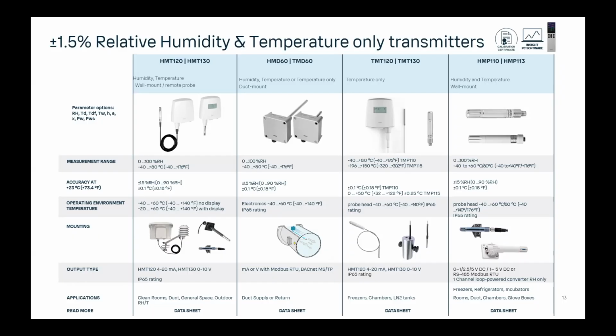It can also be installed with a fixed probe or a remote probe if you need it duct mounted versus a wall mount. And then we also have options to add a radiation shield for outdoor installation and that flange for the duct installation. Moving over to the right, we have the HMD 60. Similar specifications, just a metal enclosure that will be suitable for IP65 conditions in duct installations. And that features a long probe standard version as well as a shorter probe for smaller duct diameters.